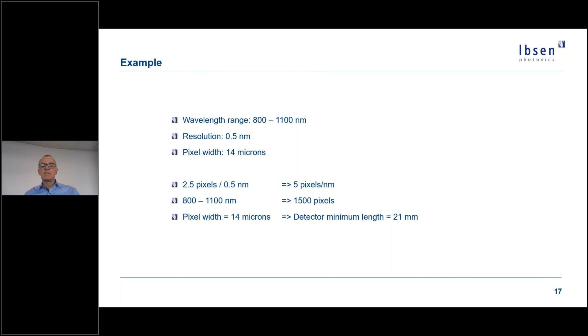To cover the entire 800 to 1100 nanometer range, that means we'd need 1500 pixels. And with a 14 micron pixel spacing, we end up with a minimum length of the detector of 21 millimeter. So that sets largely the size requirements. So the slit and optics are to some extent also locked by the wavelength range and resolution requirements.